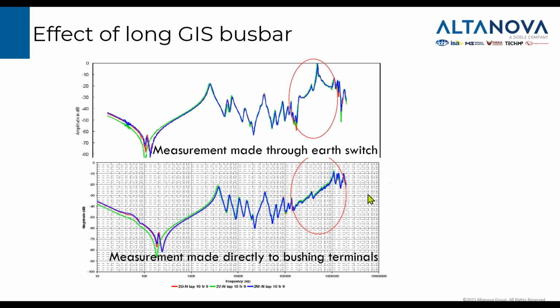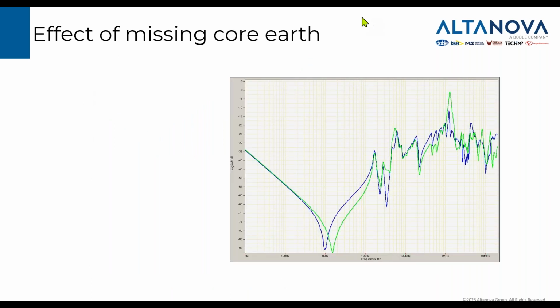And our reference was made for the same transformer in the past when it was not connected to the GIS, so we had direct access to the bushing terminals. So you can see quite a big difference in a certain region of frequencies where that busbar was included. A good thing in this case is that we have nice alignment of all three phases, so we could still treat this measurement as valid, but the effect of the busbar was clearly visible.